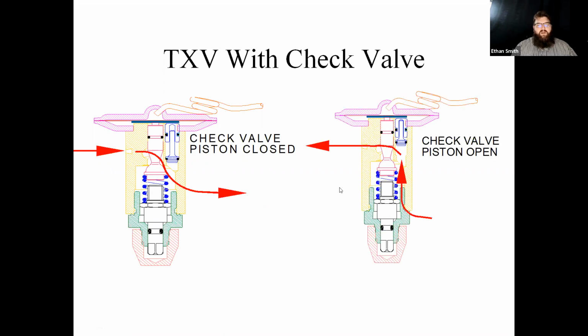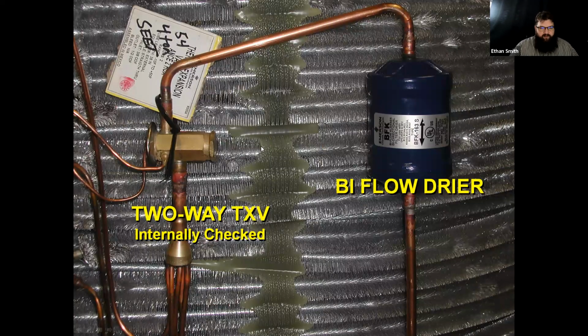So in the heating mode, if this were an evaporator, instead of refrigerant coming through the valve seat, it's coming from the other direction, and it's allowed to push past that check valve and just flow straight through the TXV without having to pass through a metering passage. So there's a two-way internally checked TXV and a biflow filter dryer. You notice the key component there is that biflow will have the arrow in both directions on that.